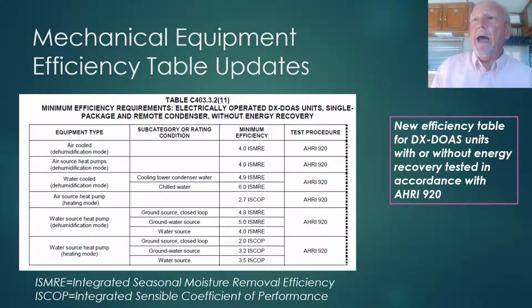Another table that's been added is for DOAS systems, DOAS air handling units, both packaged and split systems that also include a DX cooling or heat pump coil. Traditionally, DX heating and cooling equipment is not sized at 100% outside air condition. So when it's combined with a dedicated outside air system, those rating conditions no longer apply.